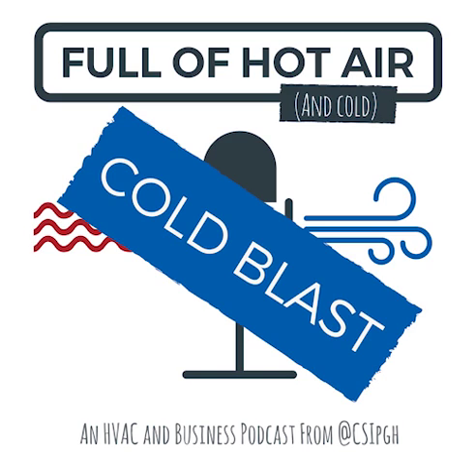What we're going to do is run the furnace, let it heat up, and then take a temperature rise. The temperature rise is the differential between the return air temperature coming into the furnace and the supply air temperature leaving the furnace. It doesn't matter what the set temp is, as long as the mode is heat and the furnace is on, because you're just testing the delta, so it doesn't really matter what the temperatures are.